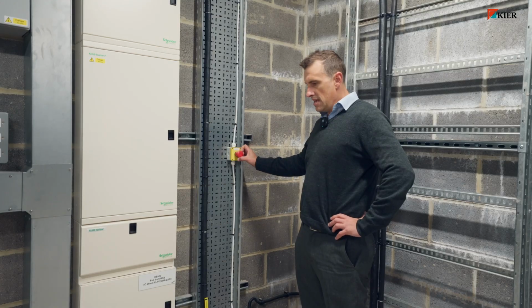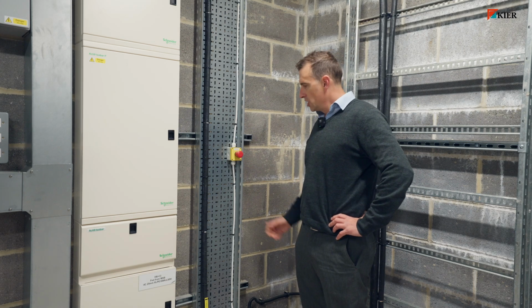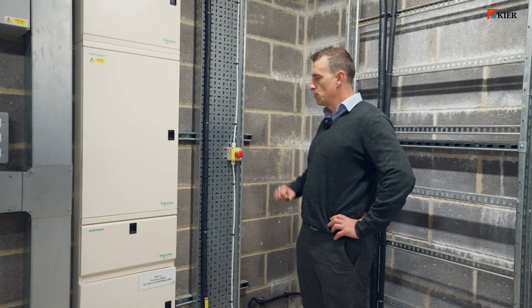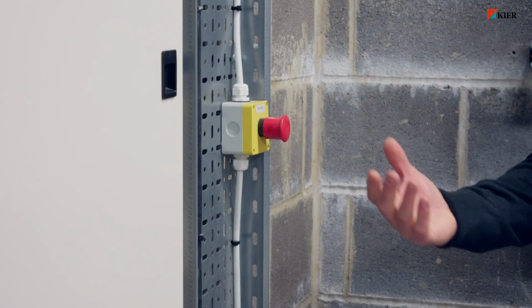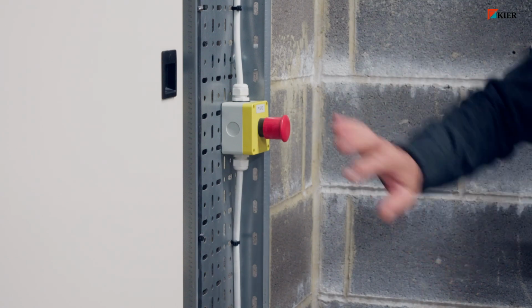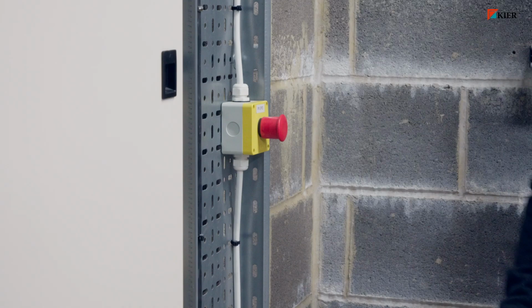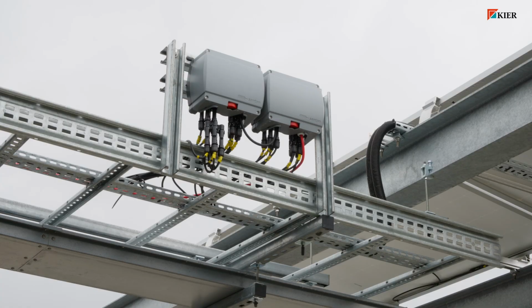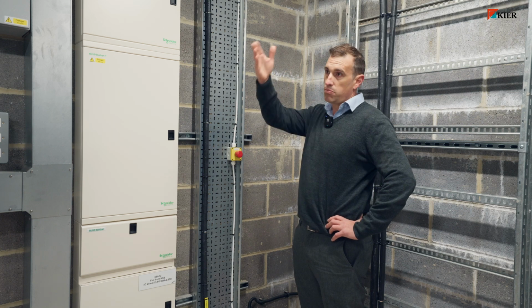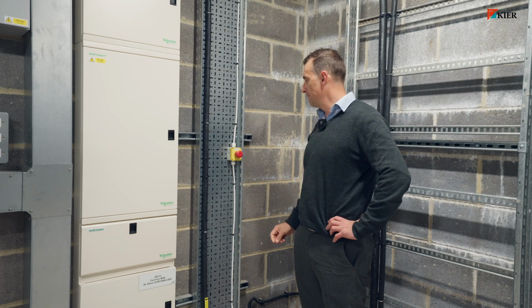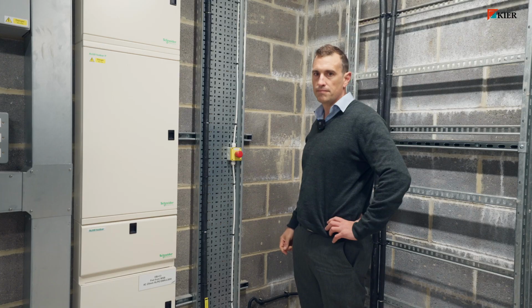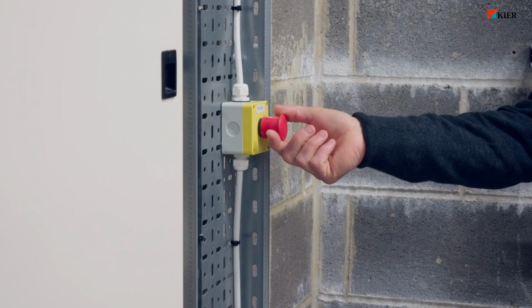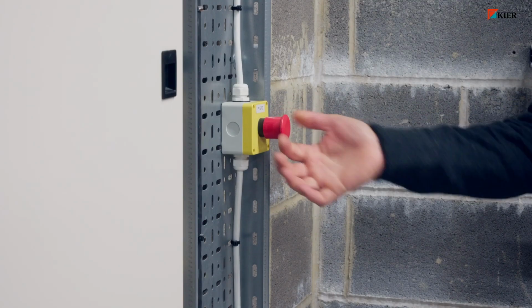This is your PV EPO, so emergency stop. So in the event of an emergency, you will obviously press it, or if there is maintenance being conducted, walk over, press the EPO button, and this changes the state of a set of contacts out in the field, which then stops the supply going over to the PV inverter. To reset it, it's just a matter of grabbing the button and pulling it back out.